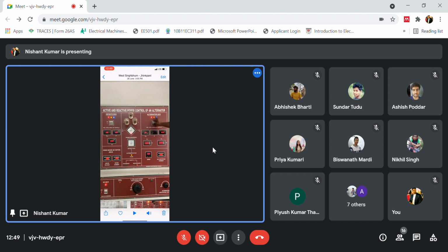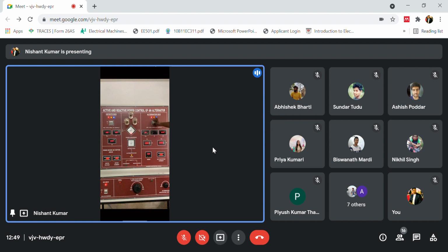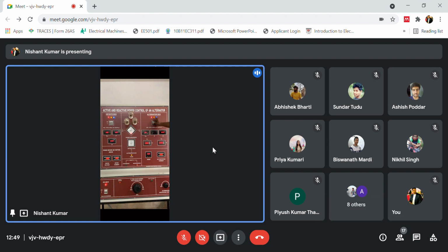Okay, in the three lamp method we also have different methodologies to adopt. They have used the one dark and two bright method. That particular sequence shows how the bulb connection is being done. Out of the three, the top one is connected to R-R, and the below two are connected in phases like Y-B and B-Y. So you could see all the segments there.